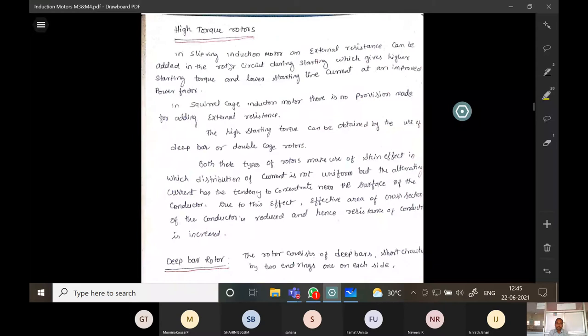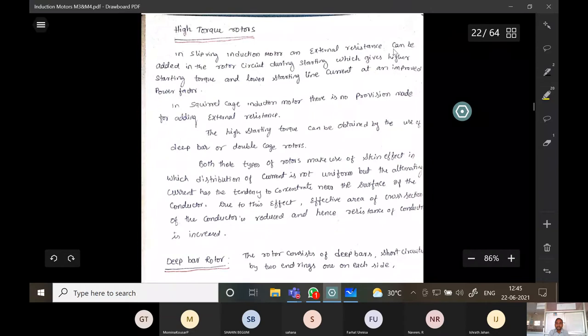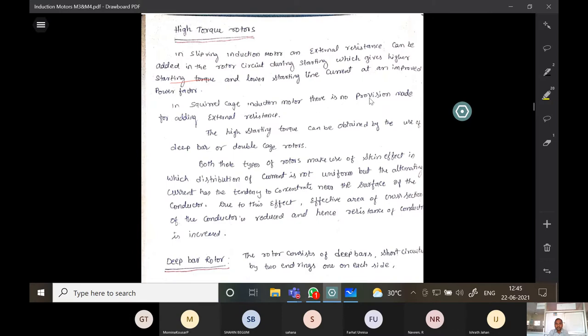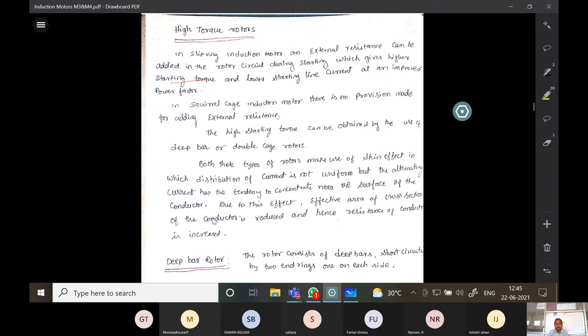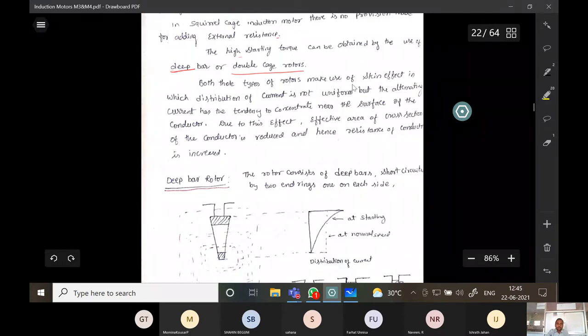The slip ring induction motor has external resistance which can be added in the rotor circuit during starting, giving high starting torque and lower starting line current, which improves the power factor. In the squirrel cage induction motor, there is no provision for adding external resistance — that is why we use the deep bar rotor and double cage rotor. Both types make use of the skin effect.